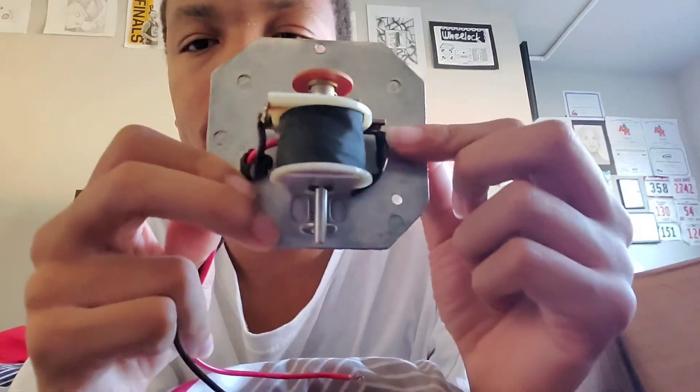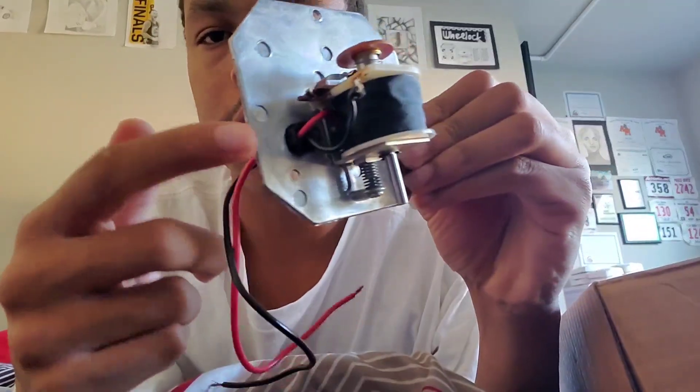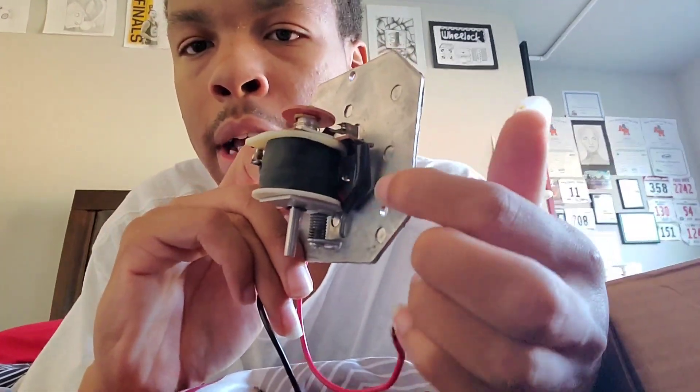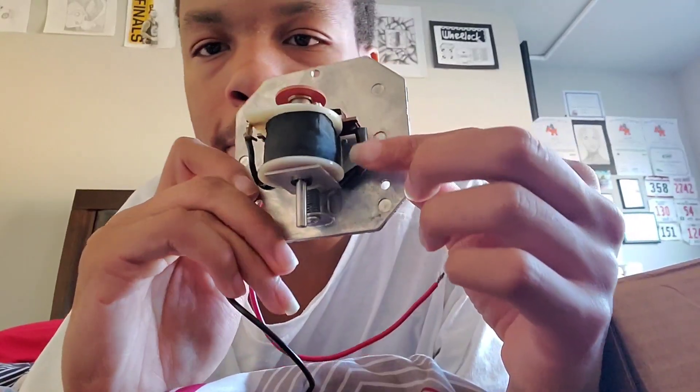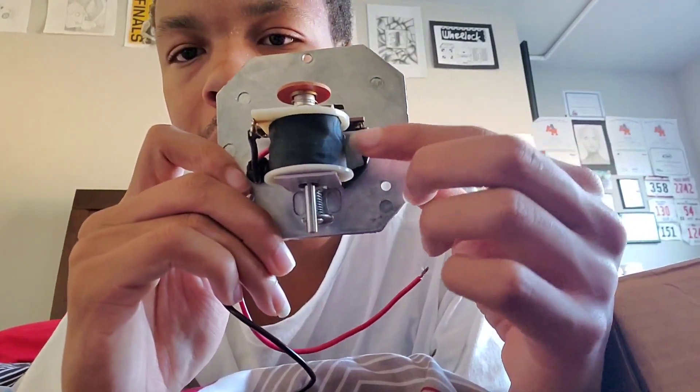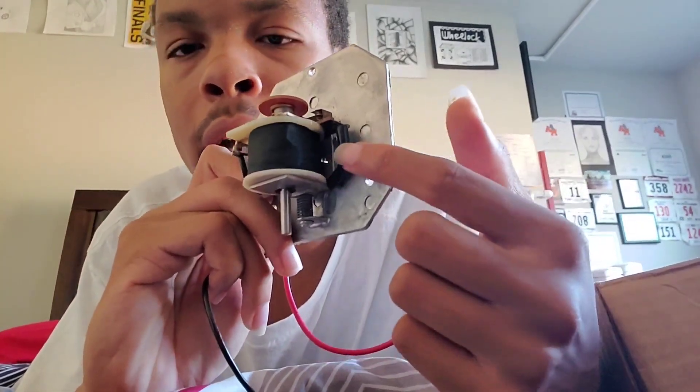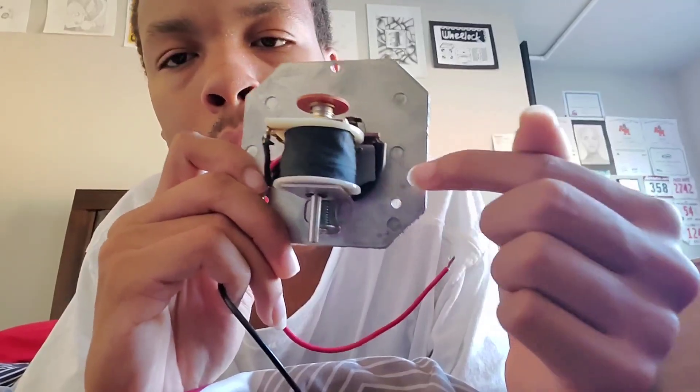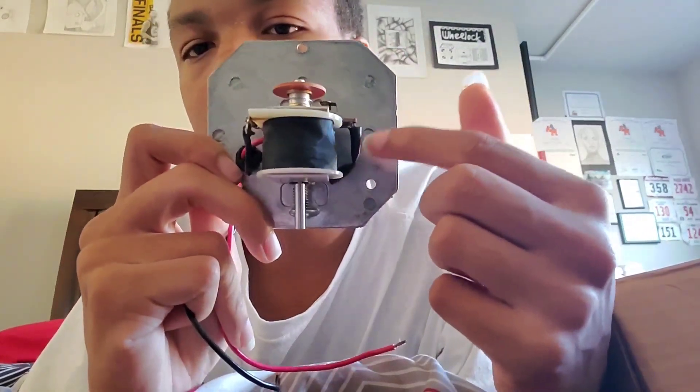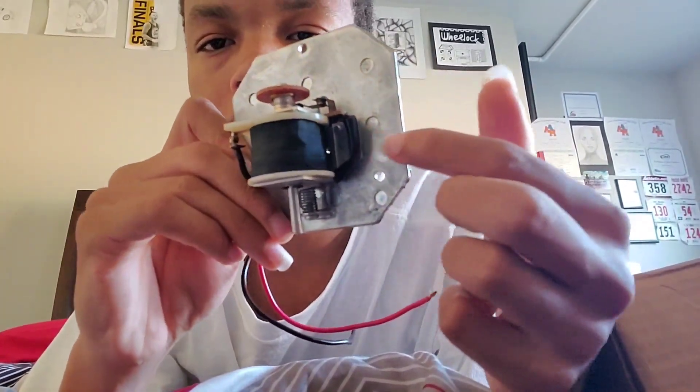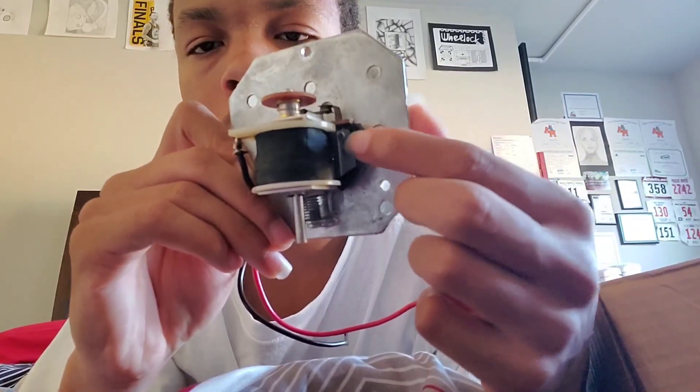This can also be a volume screw as well. This is where your two leads come in, and here is an adhesive wrap. Your diode is located in here. Like I said, it makes the current flow one way, hence having a positive and negative, and this is how a fire alarm can be supervised on an NAC circuit.